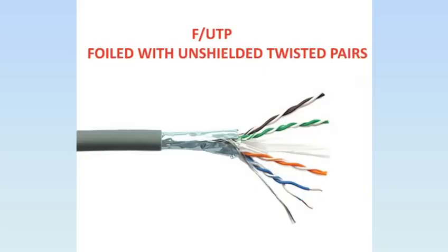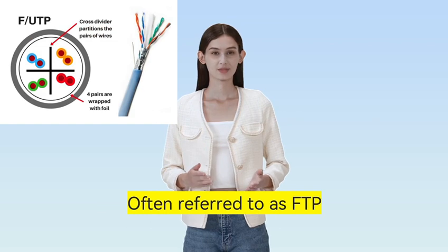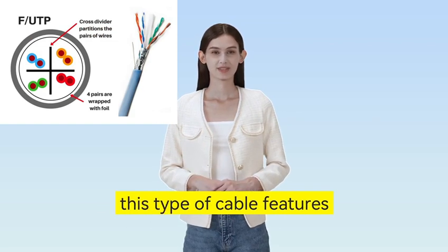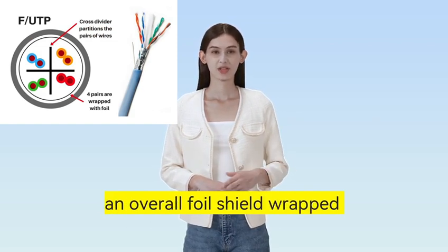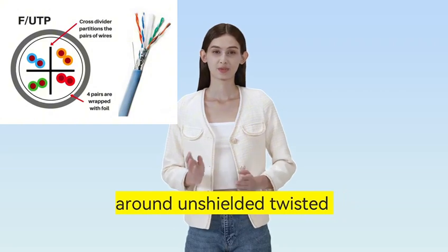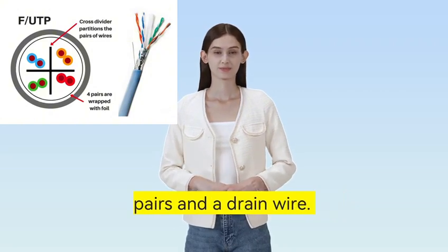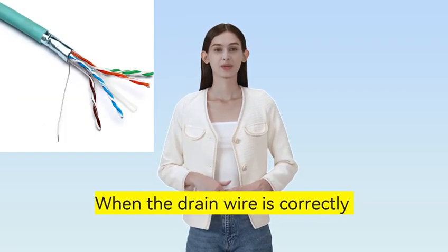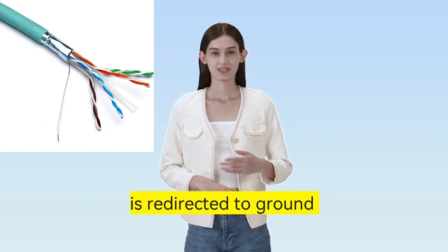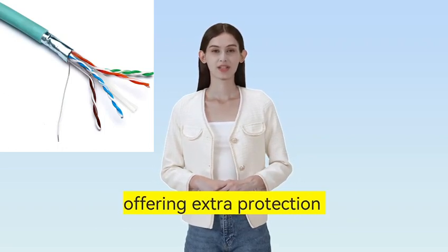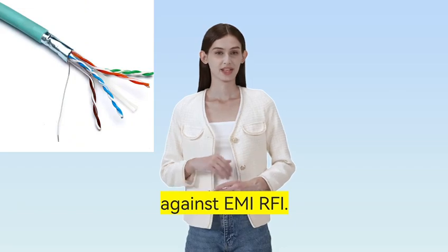F/UTP, foiled with unshielded twisted pairs, often referred to as FTP. This type of cable features an overall foil shield wrapped around unshielded twisted pairs and a drain wire. When the drain wire is correctly connected, unwanted noise is redirected to ground, offering extra protection against EMI/RFI.